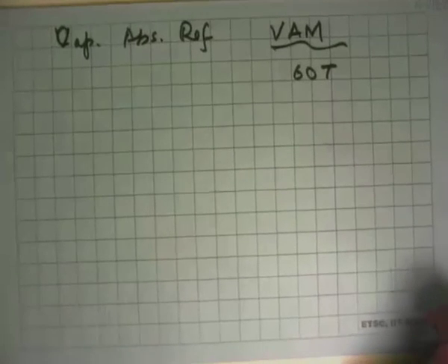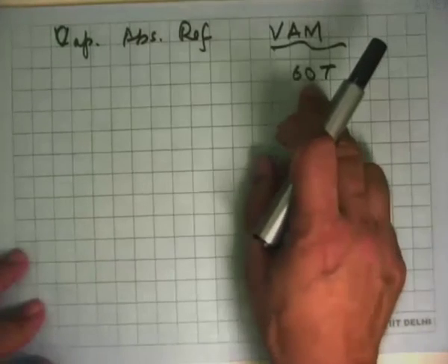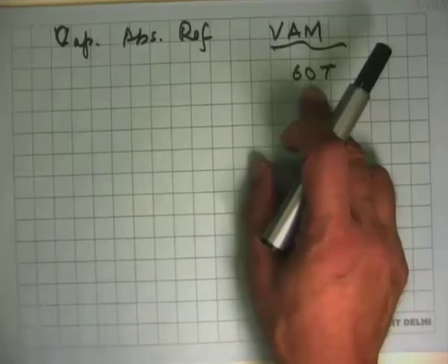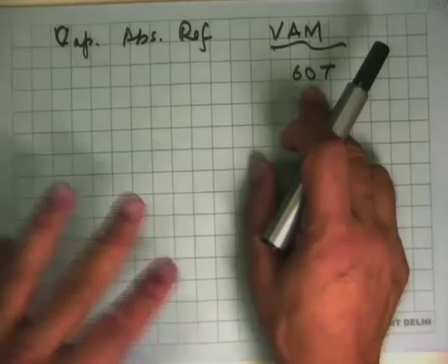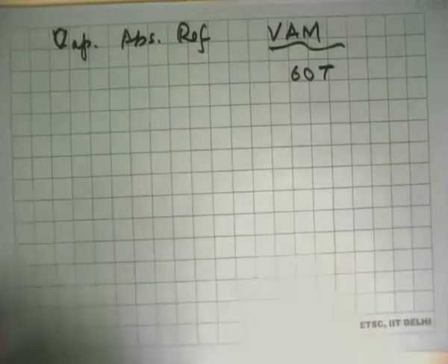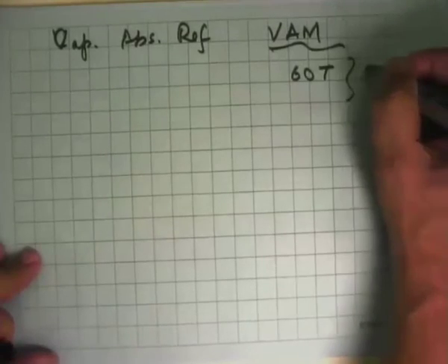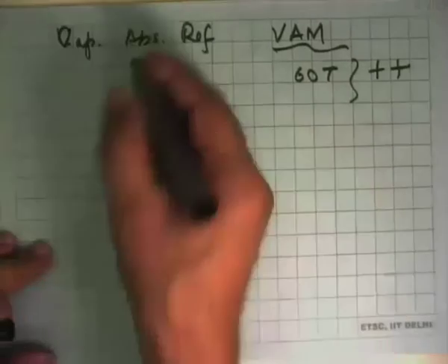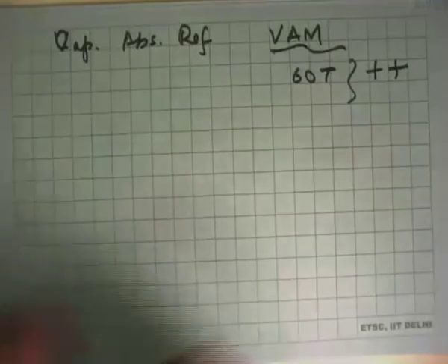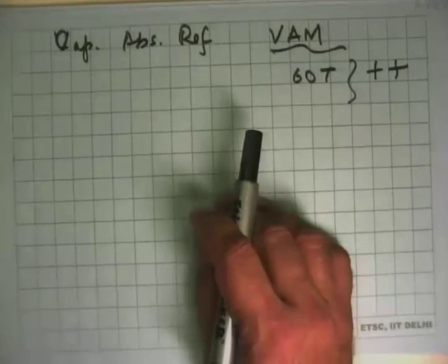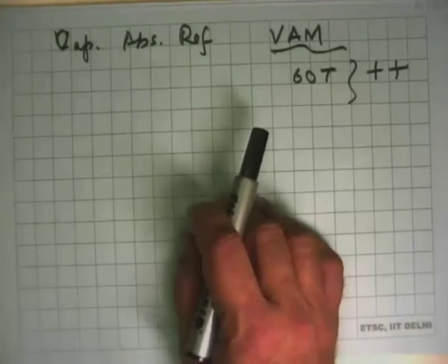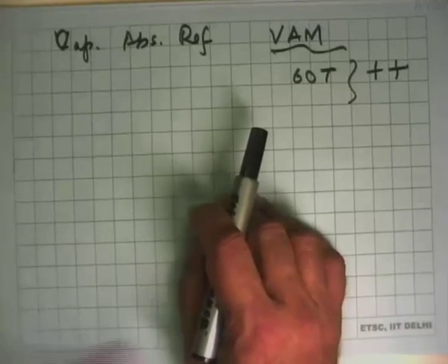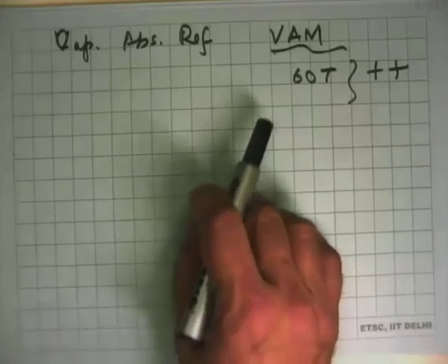And if you have a waste heat source, they are very, very good options because their electric power consumption is 1/10 or 1/20th the power consumption of a vapor compression system. So energy efficiency wise, carbon footprint wise, these are great. But the engineering is not at all easy in this case. We do not use conventional cycles. We take water and dissolve it in a salt and then we pump the solution, so the work required for pumping is very small, and then we heat it to get the high pressure vapor back, condense it and use it as the refrigerant.